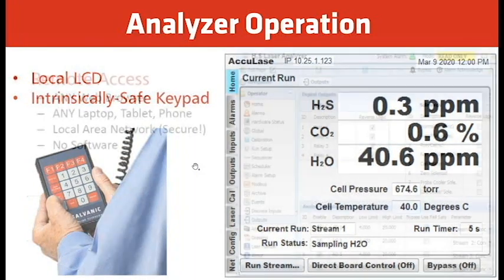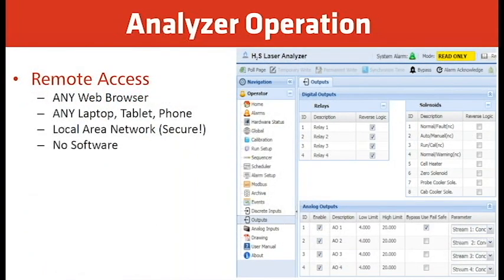These can also support remote access, which is an important feature for a lot of clients. That's done through the web-based graphical user interface, or just web-based GUI. This allows the user to view the analyzer results, also to configure analyzer settings, and to carry out manual analysis as required. The beauty of this GUI is that it's accessible through an internet browser such as Google Chrome or Firefox, so no specific software is required. It can also work simply by connecting the analyzer and typing in its IP address. Then you'll just see all the information that is available. The GUI can also operate on a local area network or simply through the direct connection of the analyzer and the PC, and that's it.